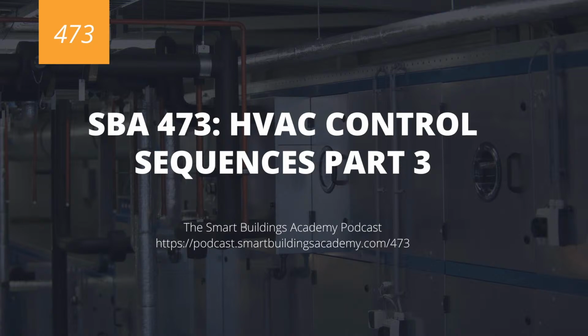I really recommend, if you're programming any HVAC system, that you have some form of maintenance mode where you disable alarms. That way folks can work on the system and not be triggering alarms and causing all sorts of issues. Okay, so we've got our three occupancy modes, right? And within our occupancy mode of occupied, we have heating, cooling, and ventilation. Let's take a look at these.